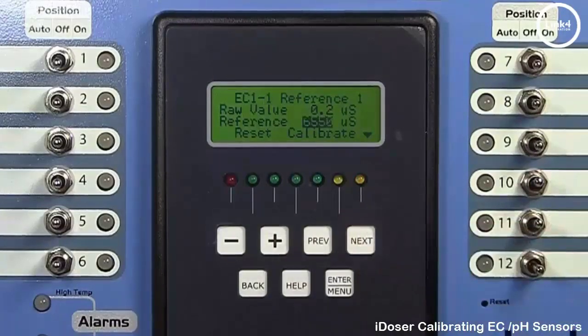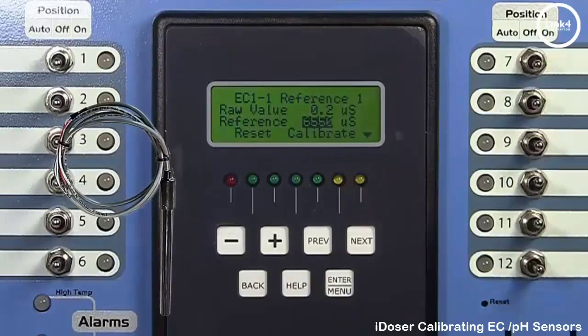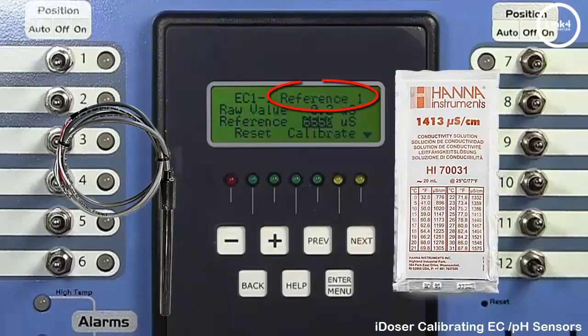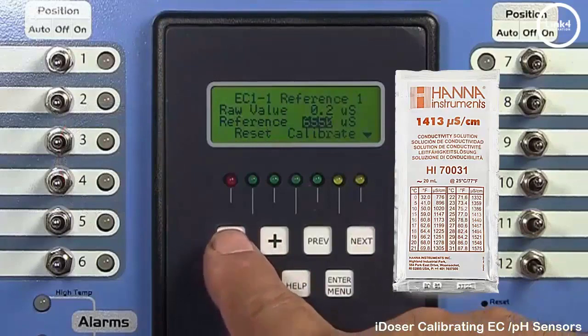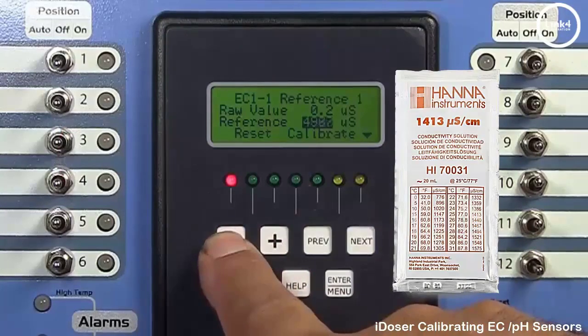Now the first sensor we're going to calibrate is the EC probe. With the EC probe, we will do a 1-point calibration with Calibration Solution using the Reference 1 screen. Now on your conductivity solution bag, it will specify in microsiemens per centimeter value you need to set your reference to. So what we will do is change this value currently in there to the value 1413.